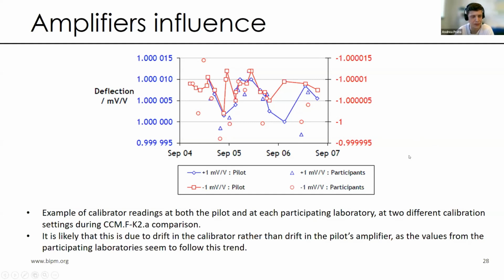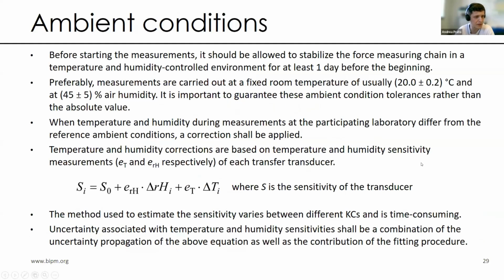So it is very important to keep this in mind in order to improve future key comparisons. The other influence factor is the ambient conditions, the environmental conditions. For this reason, different rules are adopted in different key comparisons. Mainly, it should be allowed to stabilize the force measuring chain and also the torque measuring chain for at least 1 day before the beginning of the campaign in a temperature and humidity controlled environment like the laboratory of different NMIs.